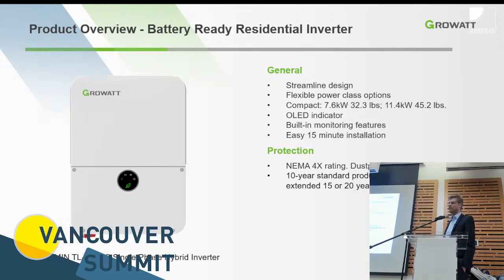The system is fully NEMA 4X rated, so you can put it outside, you can put it inside, whichever way you like. The inverter itself automatically comes with a 10-year standard warranty that can be extended all the way up to 20 years. And with the configuration app, similar to other manufacturers, you get guided through these steps into commissioning systems.